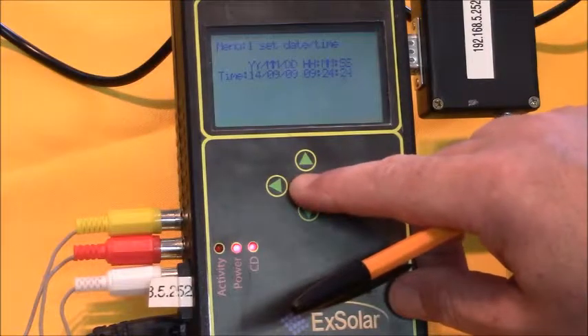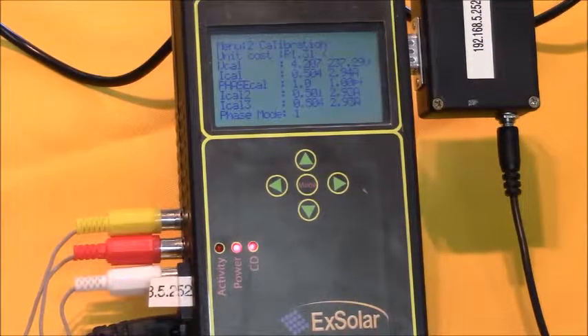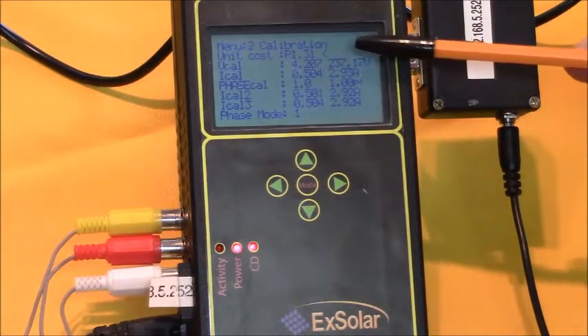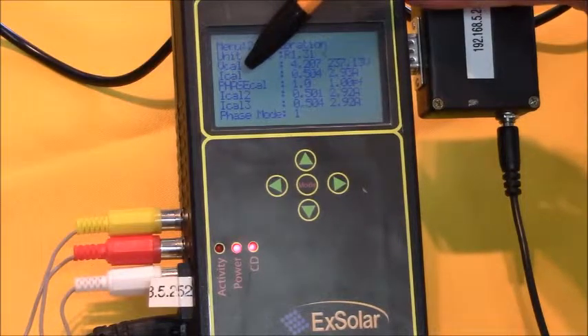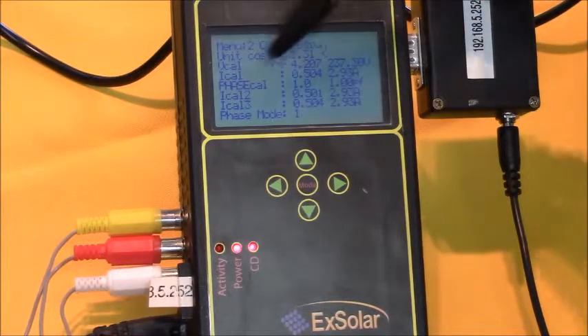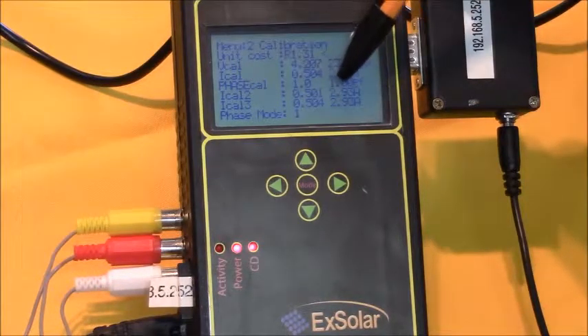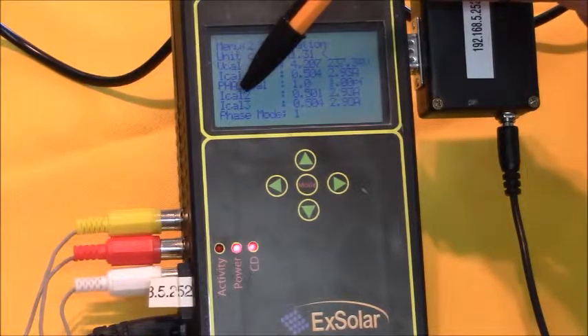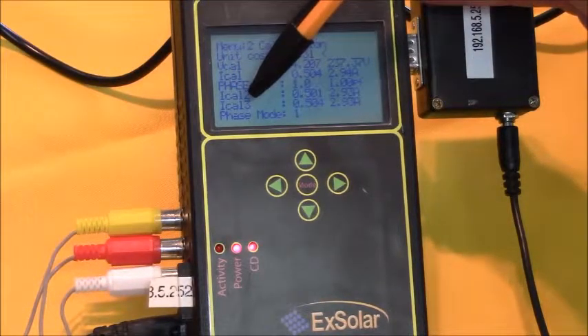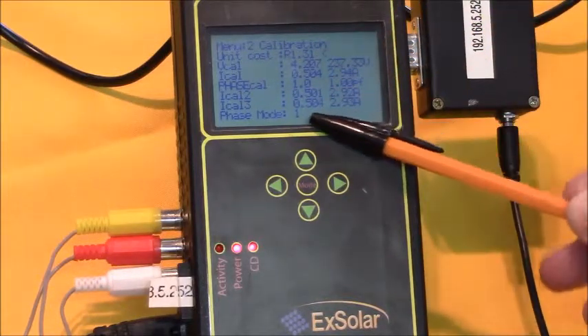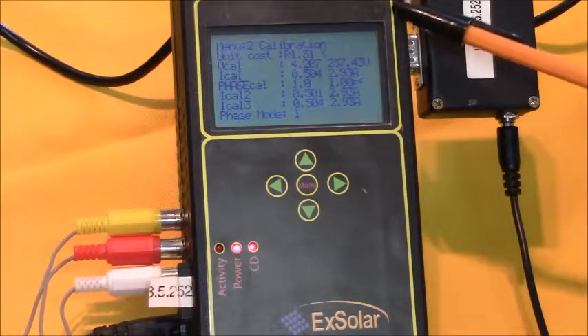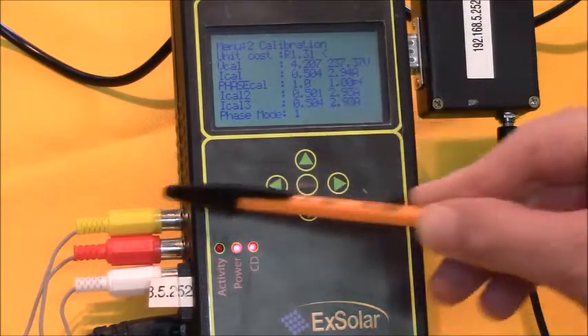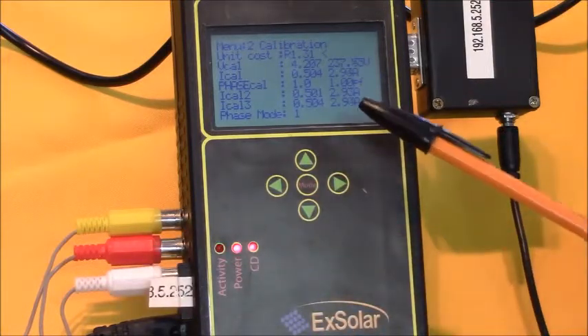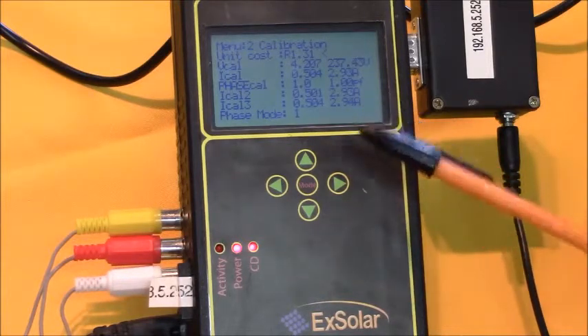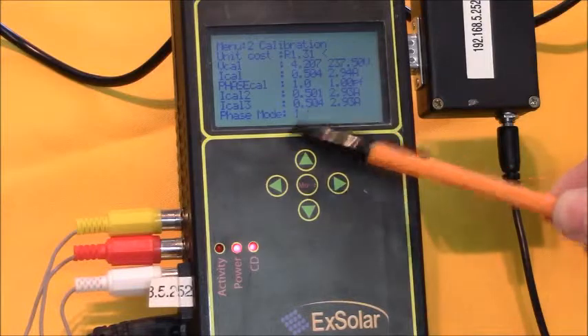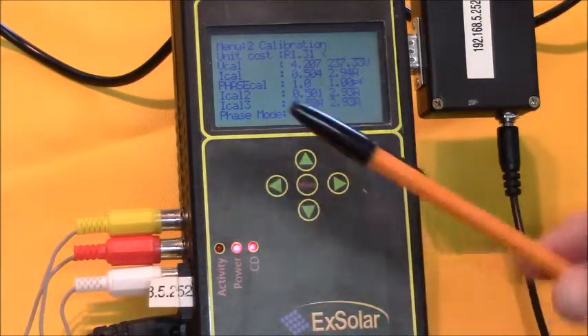Once you've completed that, push the mode button and you come to the next screen, which is the main calibration screen. With this you've got the voltage calibration, the current calibration for the first sensor, the phase calibration for the power factor, the current calibration for the second sensor, and the current calibration for the third sensor. And this bottom figure is indicating that this particular energy monitor is going to be used in a single phase application. That is, each one of the sensors is going to be measuring a different single phase item in the house. If you change this to 3, then you would put one of each of the sensors on each of the phases in the house.